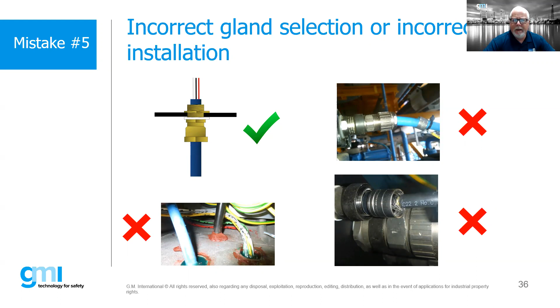So in general, cable glands should match the protection concept and should fit the cable appropriately. And when installed, no Teflon tape should be used. And then also look for things called traveling plugs. Down at the bottom, what you see is a gland with a shroud and some Teflon tape. That's not acceptable. On the right-hand side, you'll see a transmitter. You'll see a traveling plug, if you will. That's a non-certified plug. That should be replaced with a certified plug. So those are some of the key things that we want to make sure of.